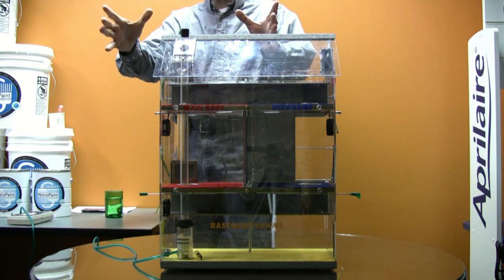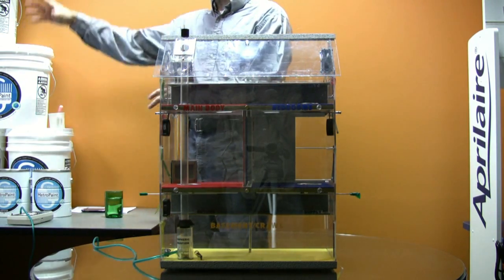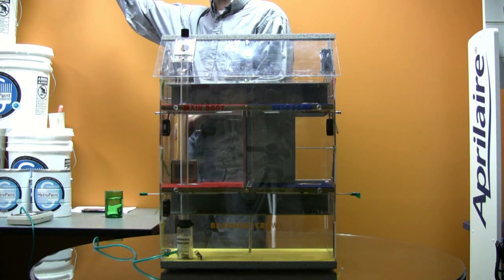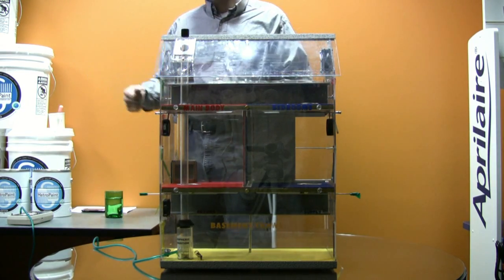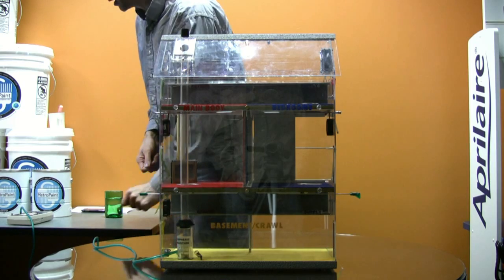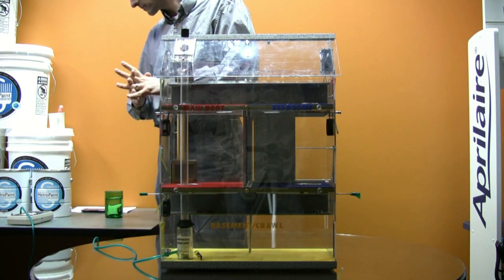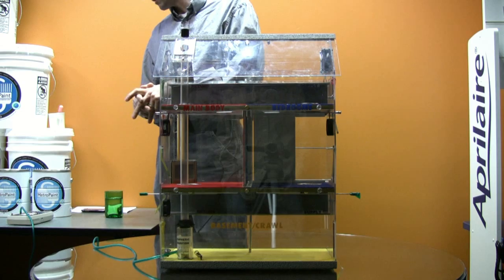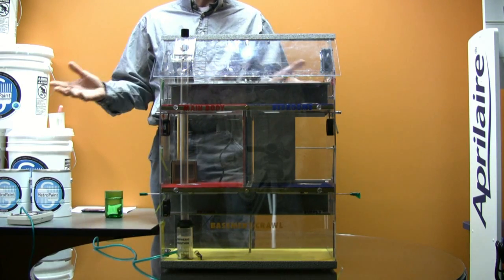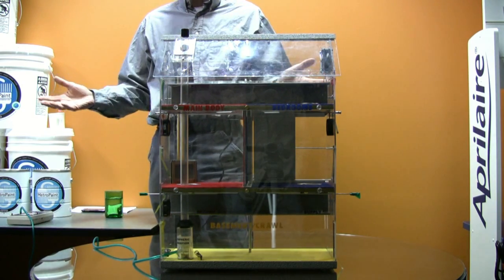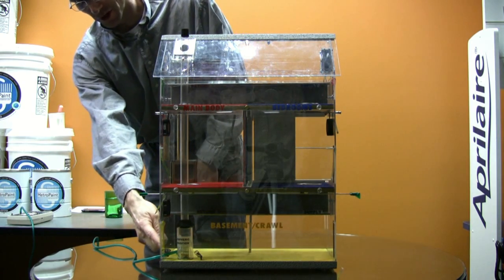You've got the water heater right here. You've got the dryer right next to it. And then they may have put in a fan as well to help it from getting so damp in that basement area. So just by turning this fan on, we've now depressurized that basement area by 0.2 pascals. Pascals is the standard unit of measure for air pressure. That's not very much. Of course, we have a big hole in our basement right there.